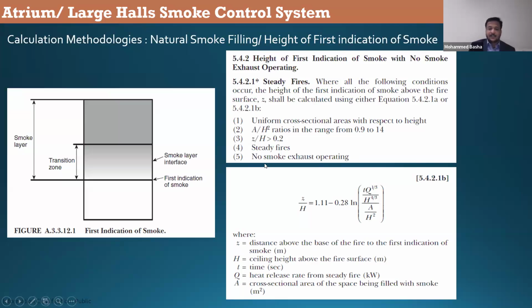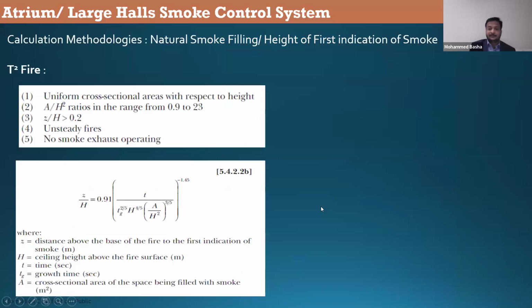We have another formula for T square fire and no smoke exhaust operating. So this is the formula. Here we need to interpolate this formula to get the T out here. Then only you will know the time in seconds. I don't know why NFPA 92 has written it like this. They must have given us one more formula to put the T here and the Z by H at this side. So we will know exactly, you can see T is time. So how much time we have for the smoke to come down.